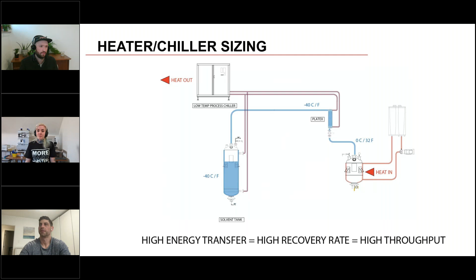You're sending hot water into your collection pot jacket, and you're boiling the butane, and then you're rejecting that heat through a chiller. Whether you're using a compressor pump or not, you're always using a chiller, and you're rejecting that heat out. And so what we're talking about here is not the temperature that you're doing these processes at per se. We're really looking at the amount of kilowatts that are transferred through this process, which is a very important distinction, because a lot of people tell us, my chiller's sweet, it goes to -80. But that unfortunately doesn't translate to the amount of kilowatts that is actually rejected.